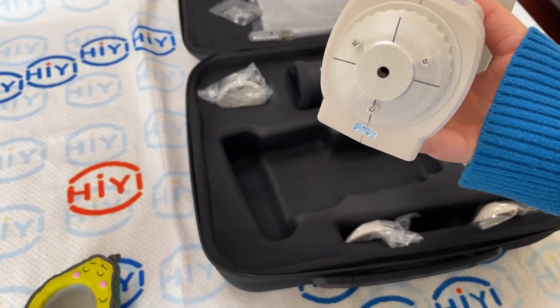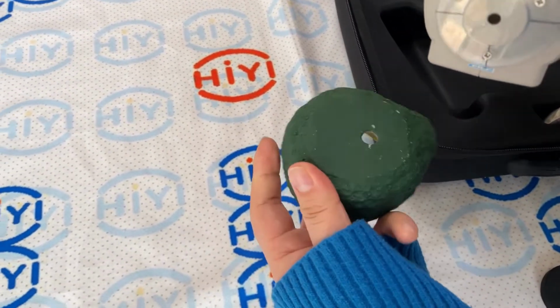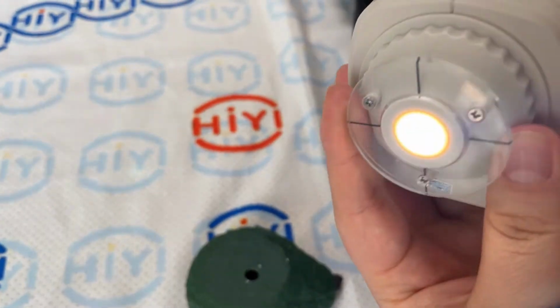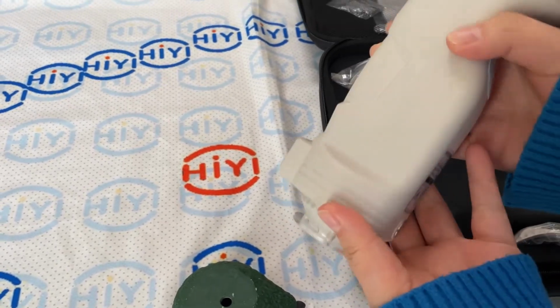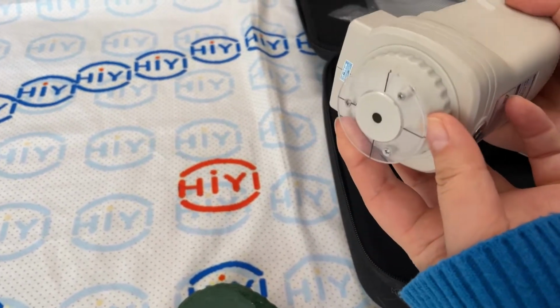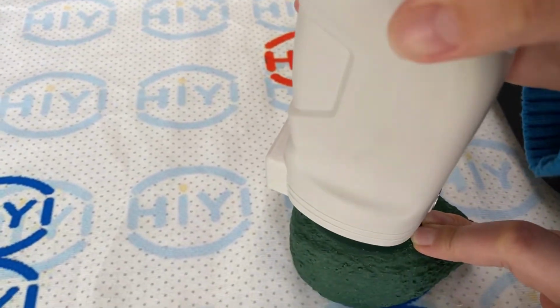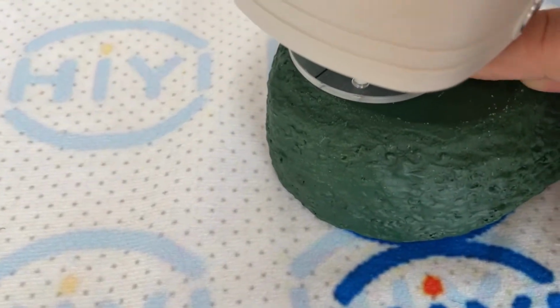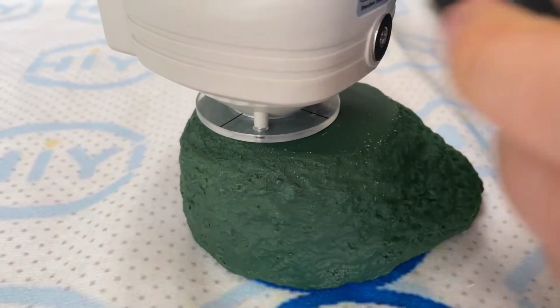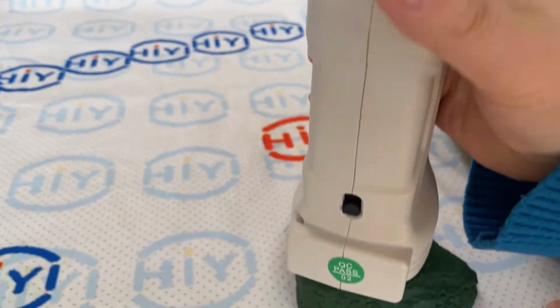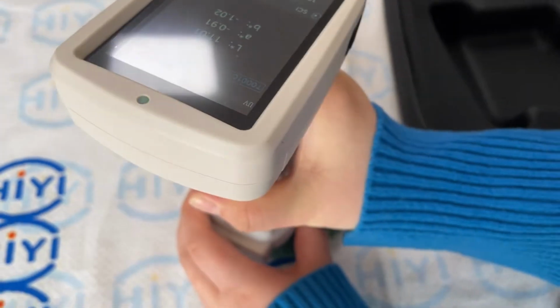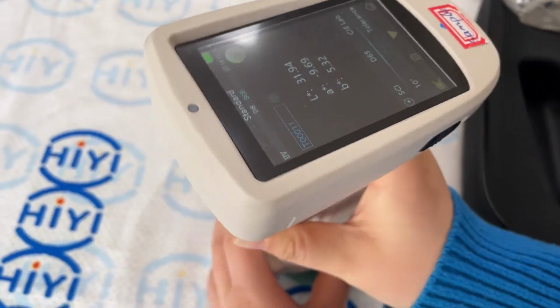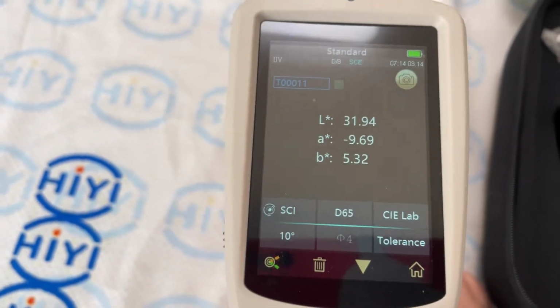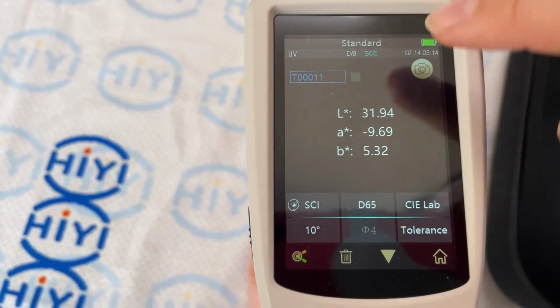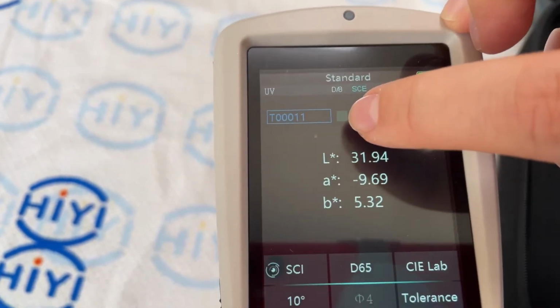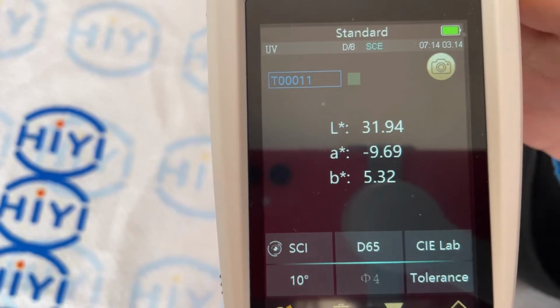Usually, if we test a smooth surface like this, we use the flat aperture to test. I press the measurement button. We use the flat aperture to test the color of a smooth surface like this. Put the aperture on the surface and then press this measurement button. Okay, now we got the value of this point, and here is the color of the point we test.